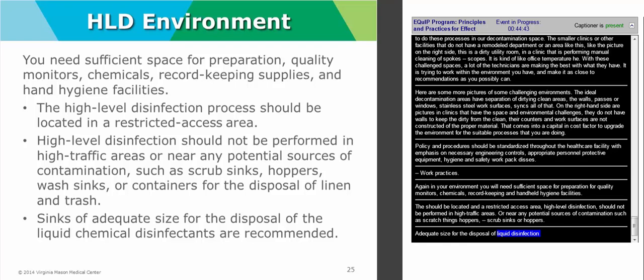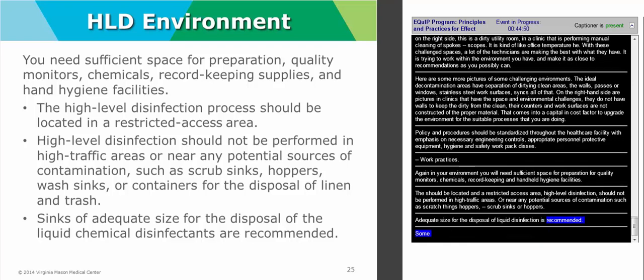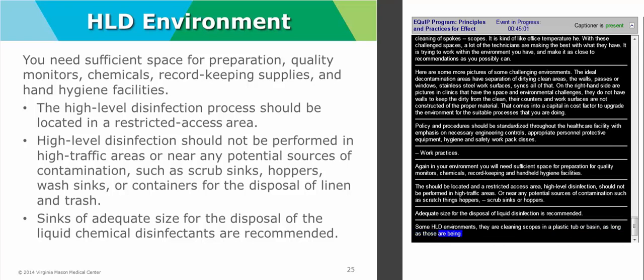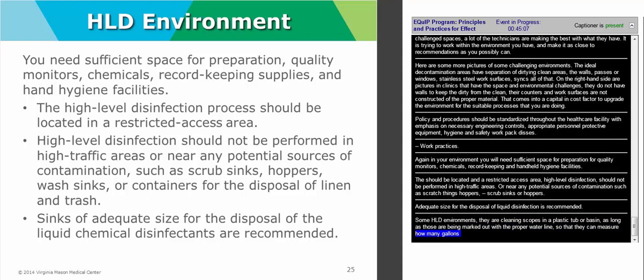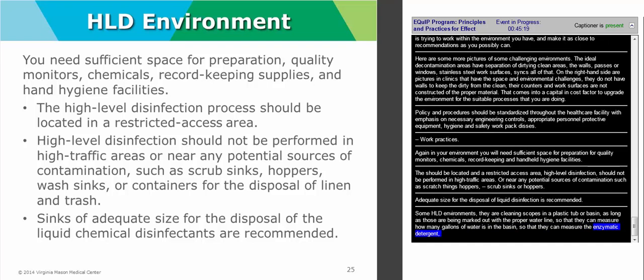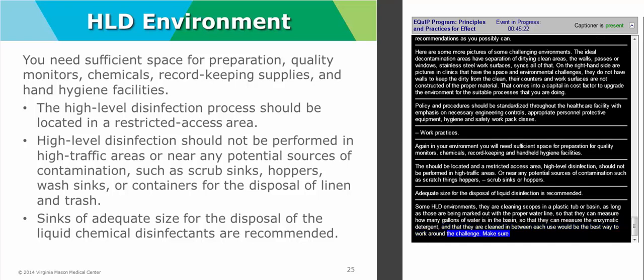And again, back to sinks and basins. Some HLD environments I have seen, they're cleaning scopes in a plastic tub or a plastic basin. Because they don't have the sinks available, that's fine as long as those are marked out with the proper water line so that they can measure how many gallons of water is in the basin, so that they can measure the proper amount of enzymatic detergents, and as long as those are emptied and cleaned between each use. That would probably be the best way to work around that environmental challenge. Also, you'd want to make sure that those plastic basins would be large enough to accommodate a flexible endoscope without having to curl it too tightly and cause damage.